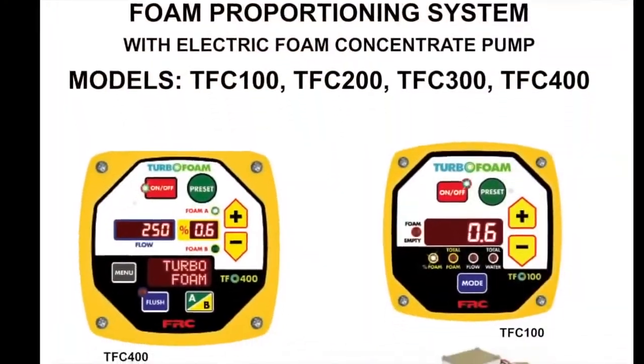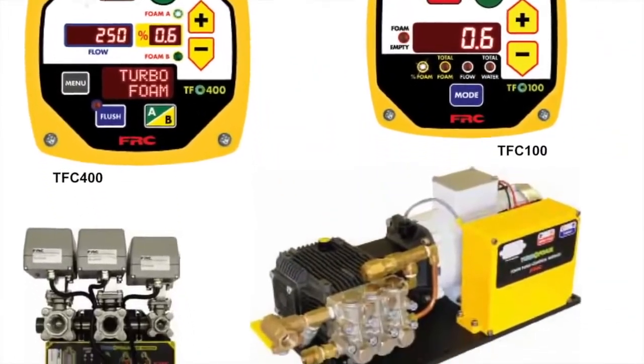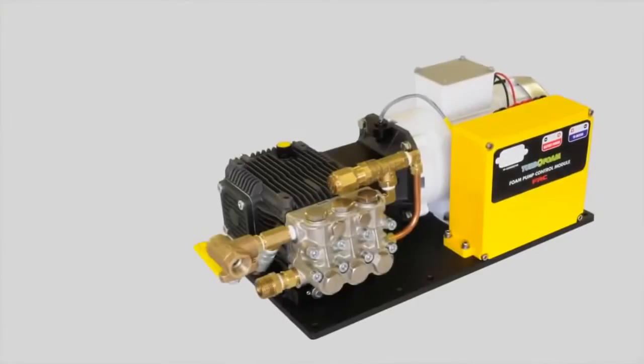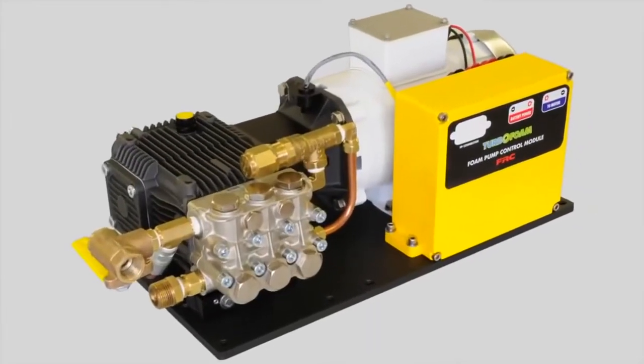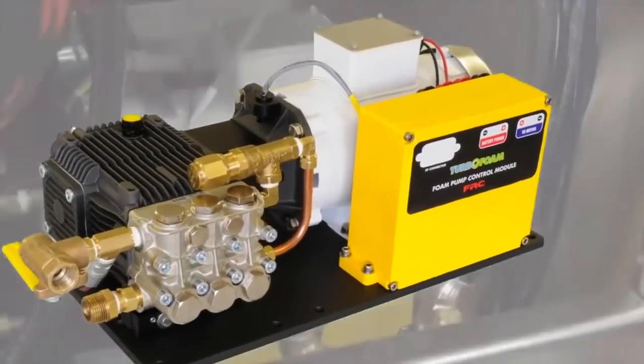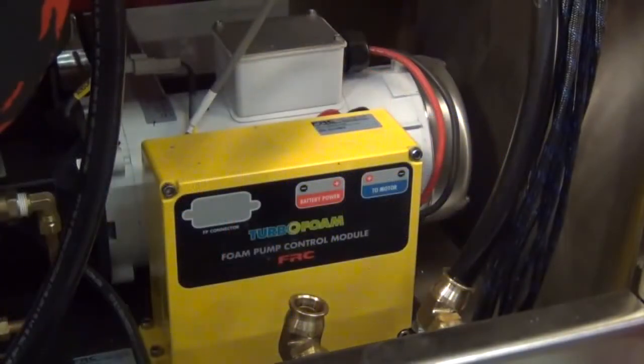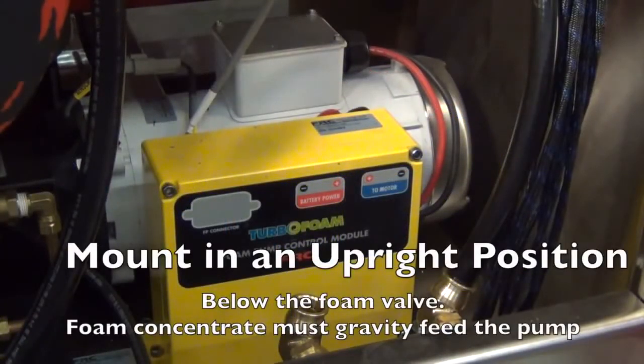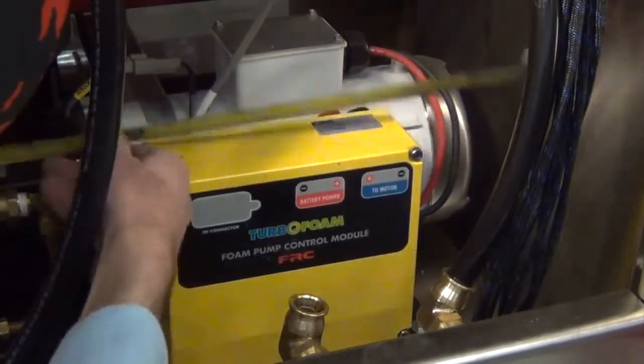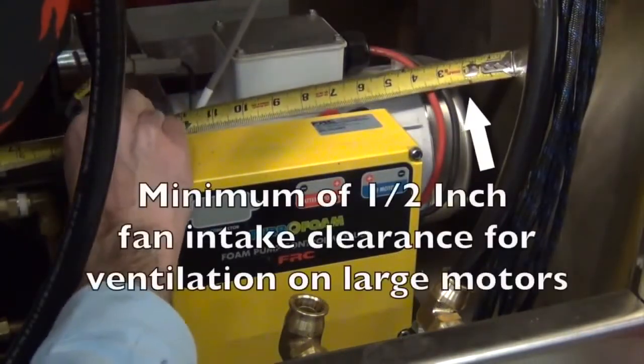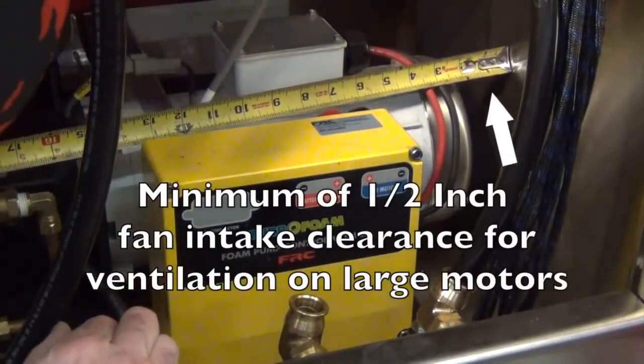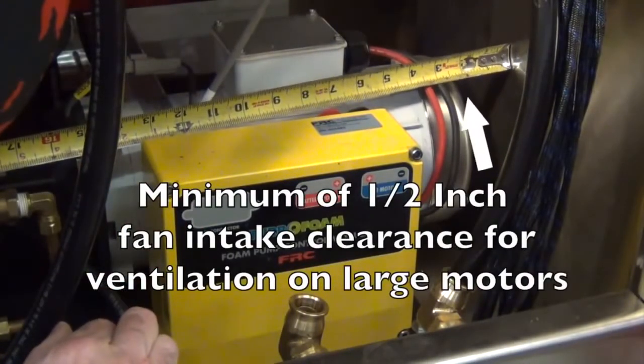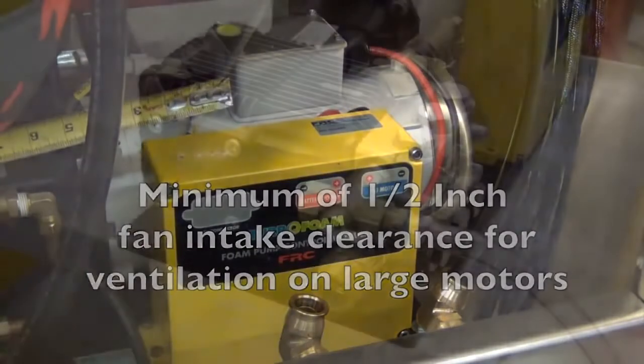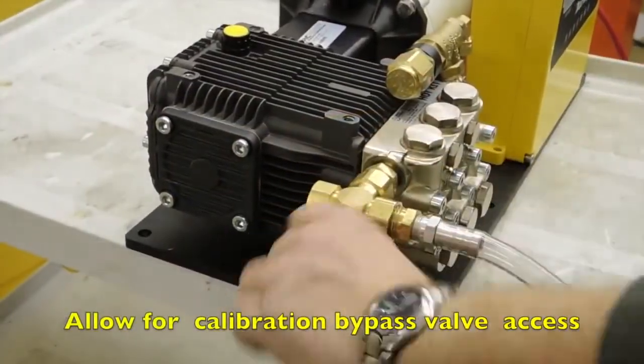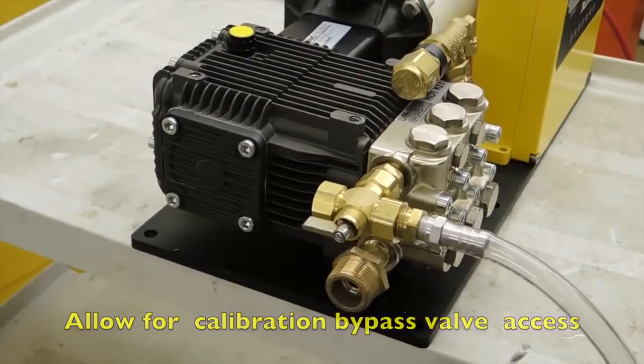We will now go over the installation of the foam pump assembly. The foam pump assembly must be located lower than the foam tank and selector valves if used. Foam concentrate must gravity feed the pump. Mount the unit in an upright position using 3/8 inch hardware. Larger pumps that have fan ventilation will require at least a 1/2 inch clearance for the fan intake. Allow room for access to the calibration valve and hose.